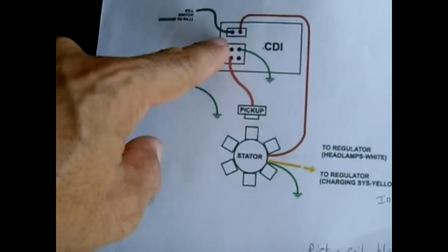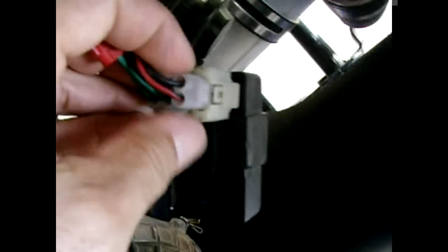So the first test is to make sure that this wire, this terminal, is not grounded when the switch is in the run position. The wire is this one right here, the top left, the black one. So the top left wire is the one we want to check to make sure it's not grounded out. We're going to release the connector and slide it out. You lift that tab and just pull it up and out. There, it's out.